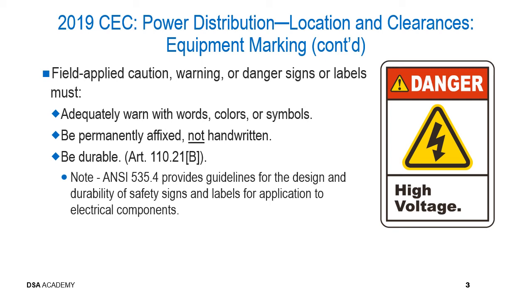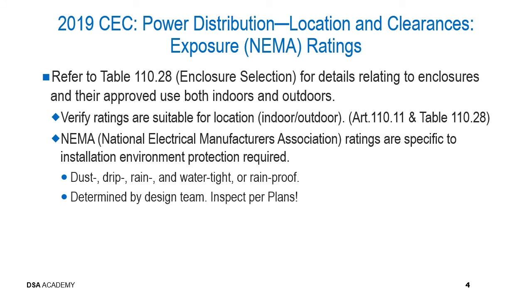One note to remember is that ANSI Z535.4 provides specific guidelines for the design and also the durability of safety signs and labels for application to electrical components. During a project inspector's review of materials delivered to the job sites, and specifically for power distribution cabinets, etc., it's important that the project inspector verifies that the cabinet itself has an approved rating for the environment that it's going to be installed in. Table 110.28, which is called the Enclosure Selection Table, provides details relating to enclosures, specifically relating to their approved use both indoors and outdoors.